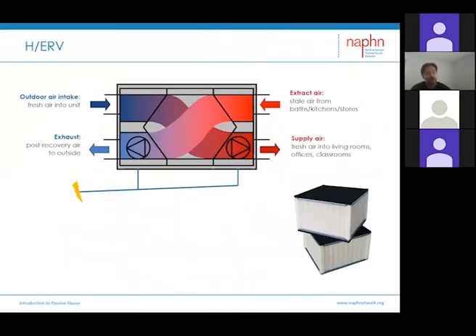To minimize the heating and cooling load of continuous fresh air, most of the time we use what's called an HRV, a heat recovery ventilation unit. The fresh air coming in passes through a heat exchanger and picks up heat in winter from the air being extracted. So the fresh air coming into the house is way warmer than the outdoor temperature. For example, when it's about 0 degrees outside, and you're extracting air at around 65-66 degrees, the fresh air will come inside at more than 50 degrees. It's a very efficient and inexpensive way to warm up your fresh air.